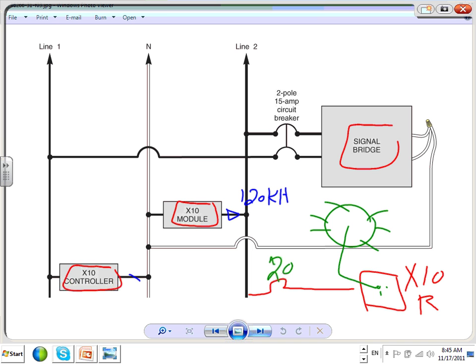How do you send the signal on the power line? From a telecommunication point of view, and correct me here, Chris, if I say something wrong, conductors are like highways. I can put a car on the highway, that will be one signal, my voice, or I can put a truck on the highway, that will be the power signal to power the equipment, or I can put a motorcycle on the highway, that will be another signal. So on the same cable, you can send multiple signals in telecommunication. Unlike power, where you send only one signal for the most part, one frequency signal, a 60 hertz frequency signal on a power circuit. On the same line, you can make other signals ride the same cable.